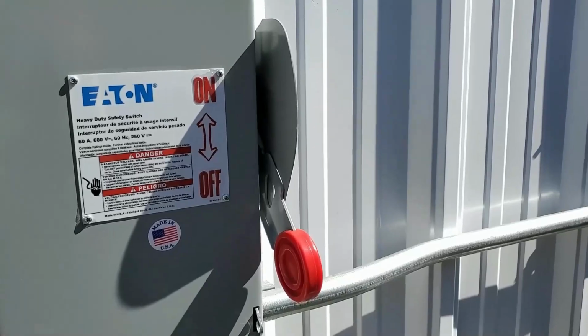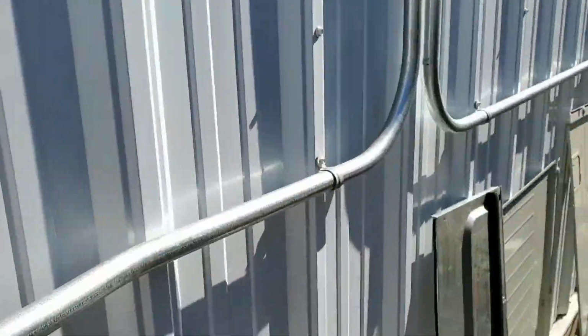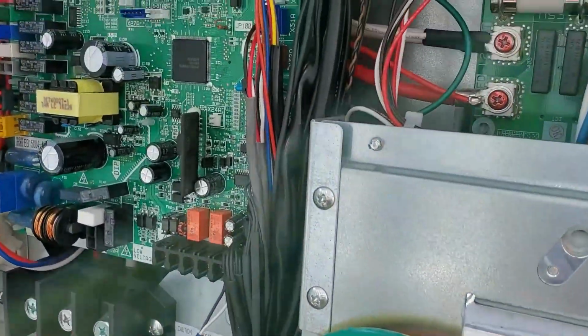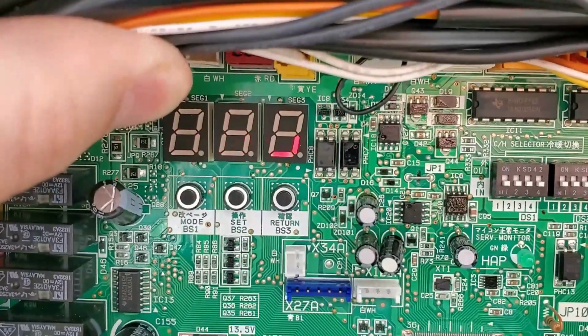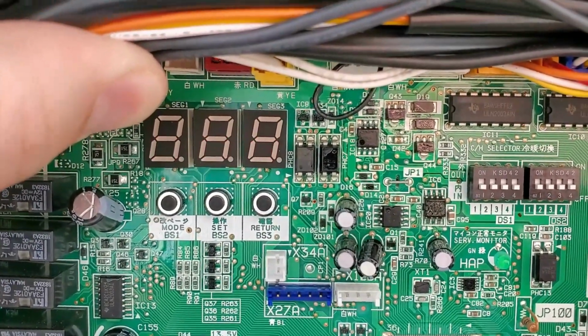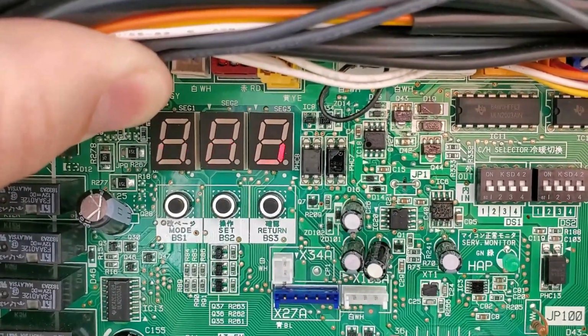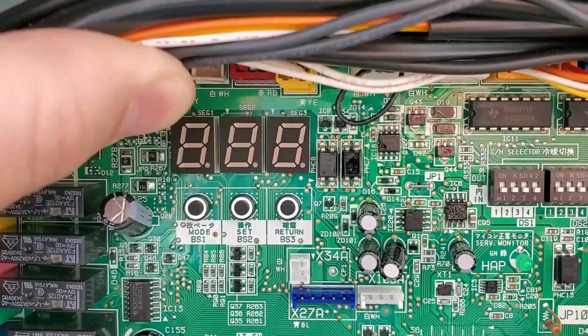Now, if this is the first time you've ever powered up the outdoor unit, say for whatever reason you never powered it up the night before or the day before to get that 6-hour minimum on time, this is the first time you're powering up that outdoor unit, that's fine. Power it up, and then you're going to sit and wait, because the outdoor unit needs to initialize, and this initialization process can take up to about 15 minutes. It shouldn't usually take longer than this. There is a potential that it takes up to 30 minutes, which we'll talk about here in just a second.